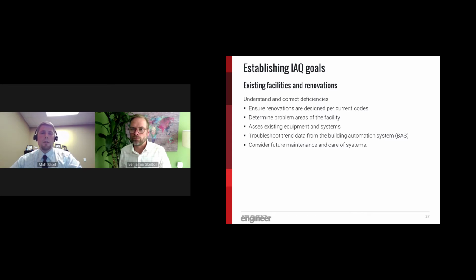Take a tour of the current facility and familiarize yourself with the space, how it's being served, and from what equipment or systems. Even if you're intending to remove the equipment or systems, it's important to assess these areas so that the newly specified and constructed systems don't experience the same issues. If it's available, it's helpful to troubleshoot trend logs from the building automation system, especially for some of the areas the owner might identify as a problem area of the building.